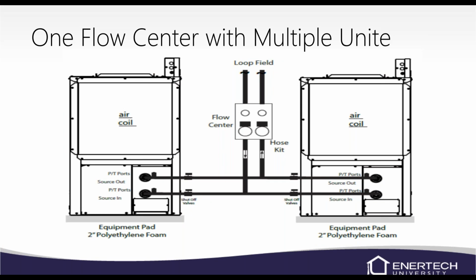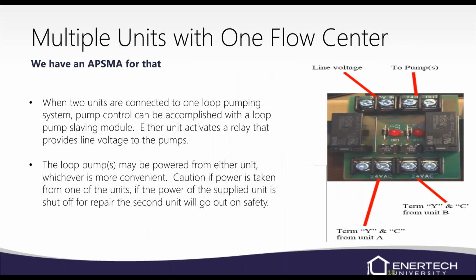You can have one flow center with multiple units. If you've got a pressurized flow center like this, two units is the most you can do. And with this, you'd want to get the pump sharing module so that when one unit or the other is calling, the flow center will come on. This is basically just a setup for a single flow center with two units on the same loop field. This is the pump sharing module.